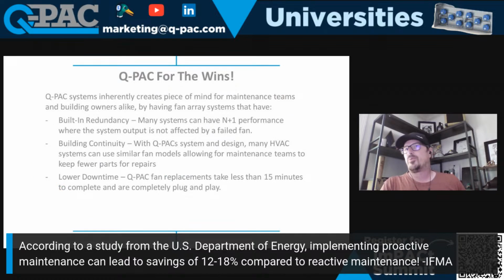We touched on why we'd do a retrofit system for older style buildings, and the biggest reason is to add some sense of redundancy into their system. A lot of these systems, if a belt goes out, a motor goes out, a pillow block bearing, anything that can knock that system out of place, they don't tend to have backup support. A motor change out could take half a day or longer depending on the availability of the motor and the time to replace it, or what component failed. So having redundancy gives the end users and maintenance crews peace of mind that if a fan were to fail, nobody's panicking.